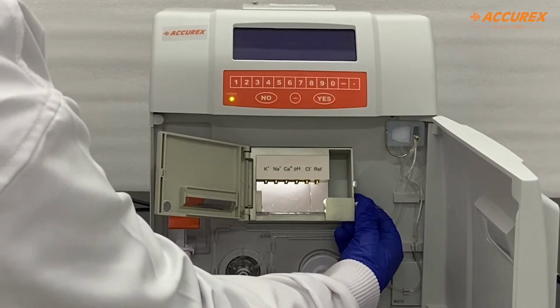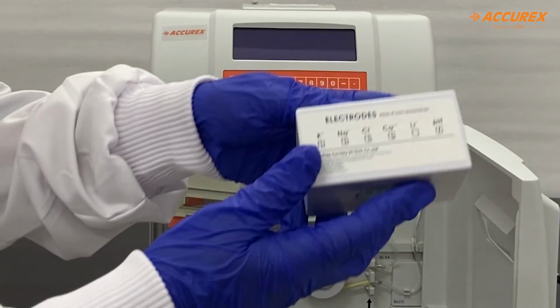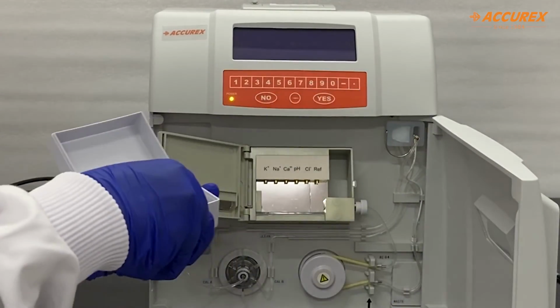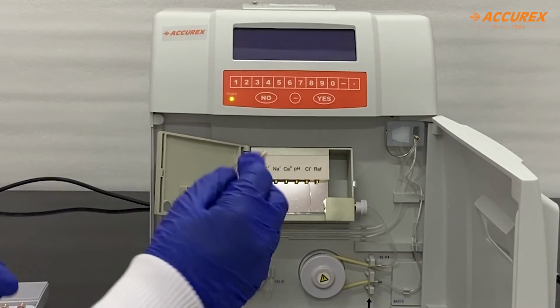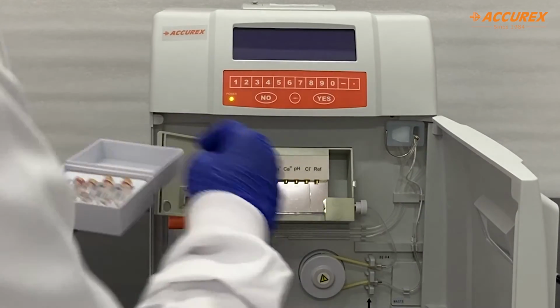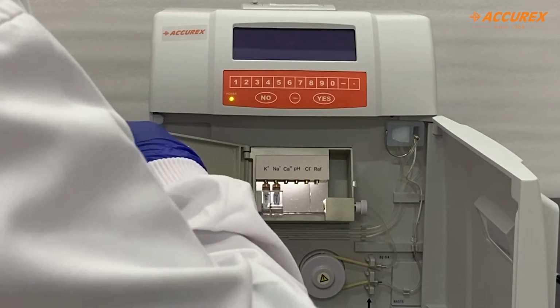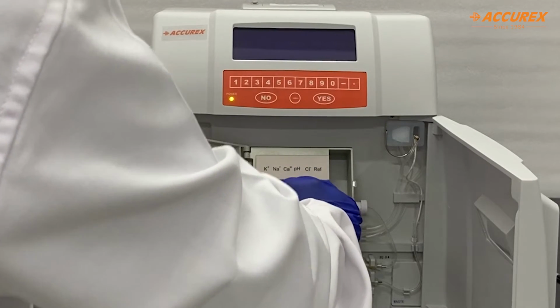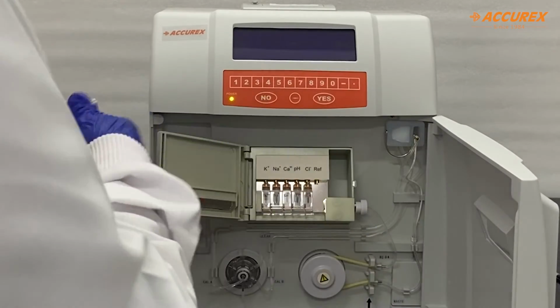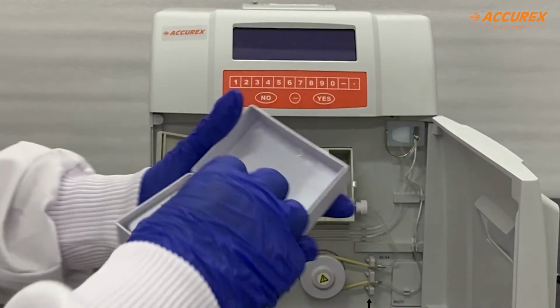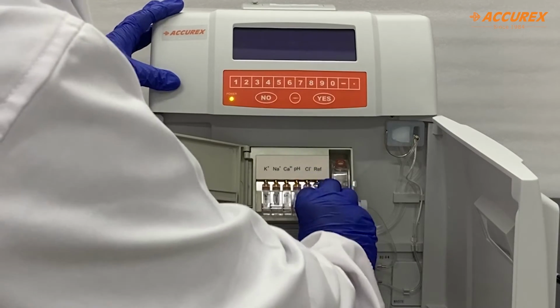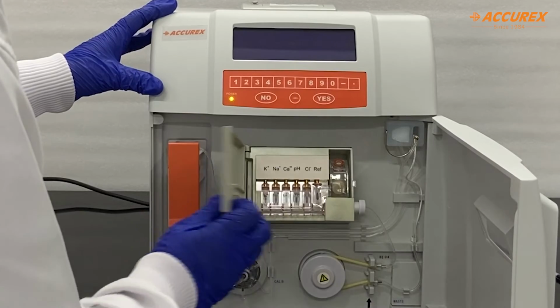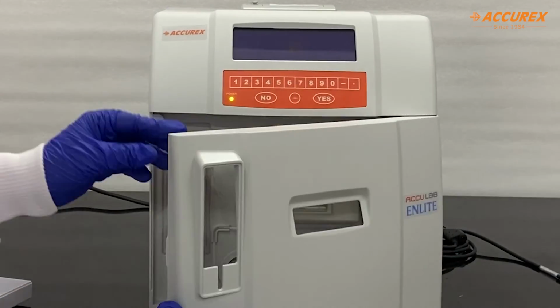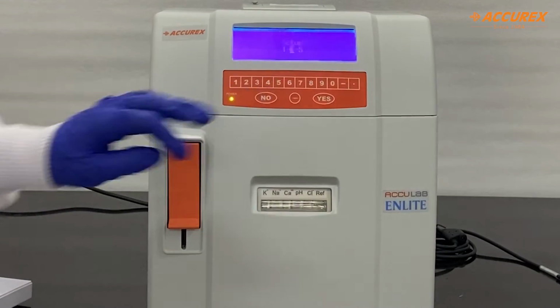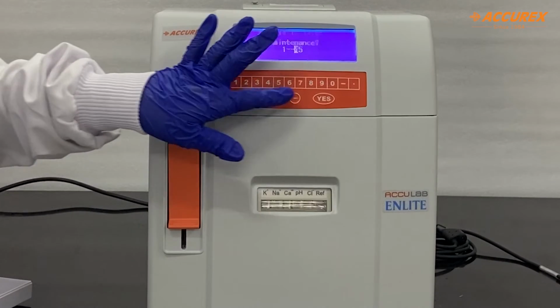Pull out and twist the knob of measuring chamber to release it. Take electrodes. Install electrodes one by one. Then we have to connect reference electrode. Then return, close the measuring chamber and front panel, and calibration will start after it.